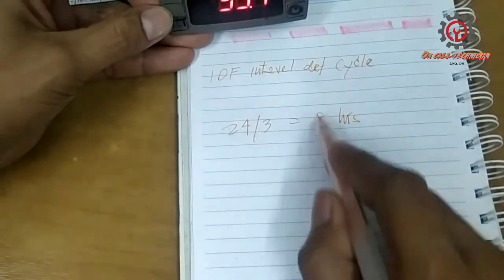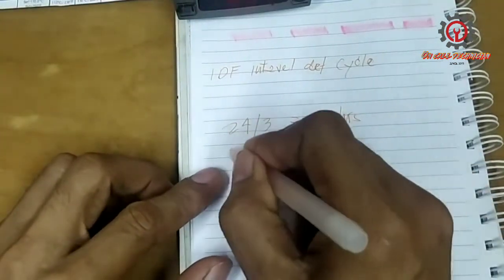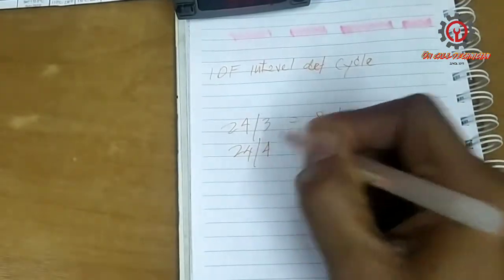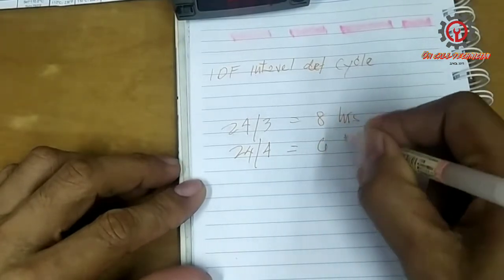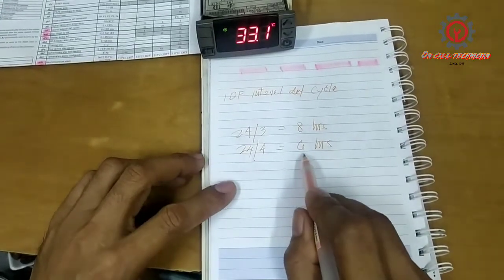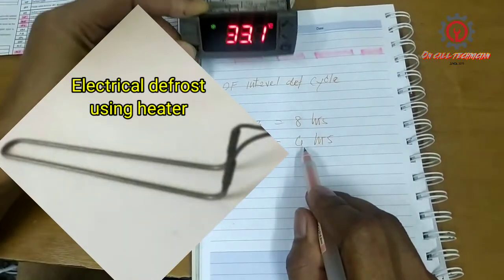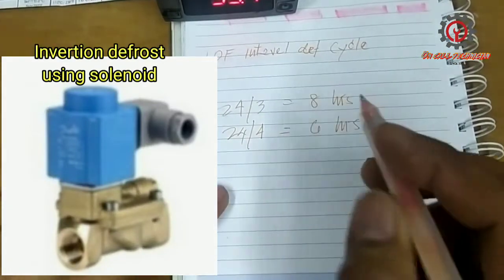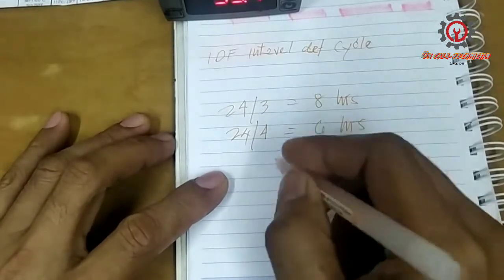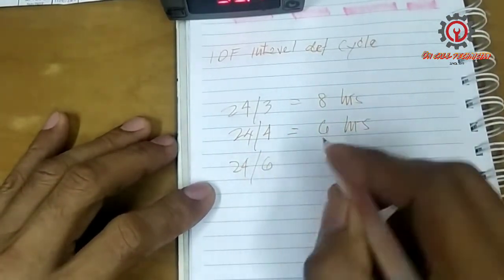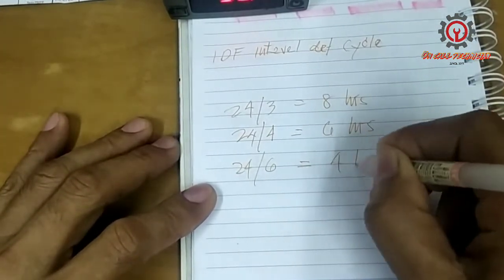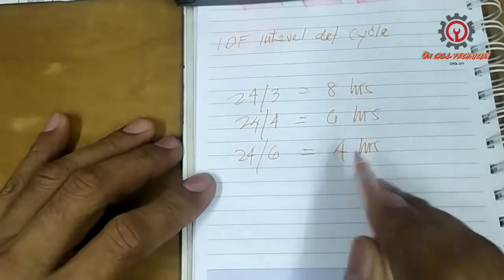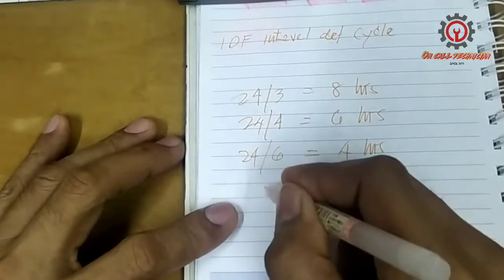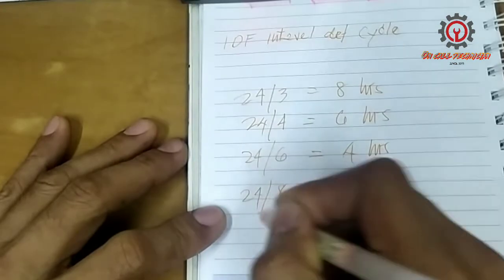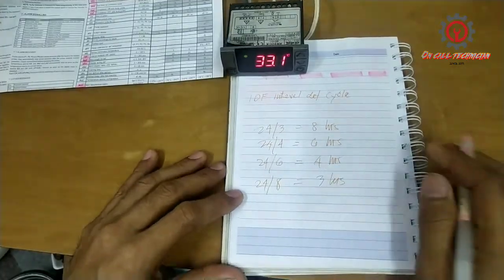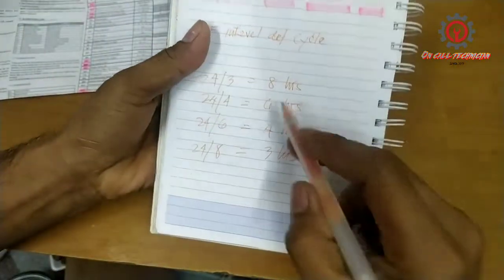It depends on how you set the hour here. For example, 24 divided by 4 hours is equal to 6 hours. So every 6 hours this control will engage the defrost heater or defrost hot gas, or it will defrost. For example, I want to choose 6. 24 hours divided by 6 is equal to 4 hours. So every 4 hours my unit will defrost. And what if I want an 8? Okay, 24 divided by 8 is equal to 3 hours. Now the question, guys, is which of these 4 I'm going to use.